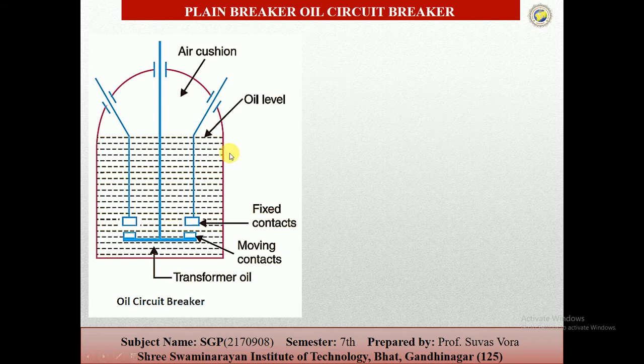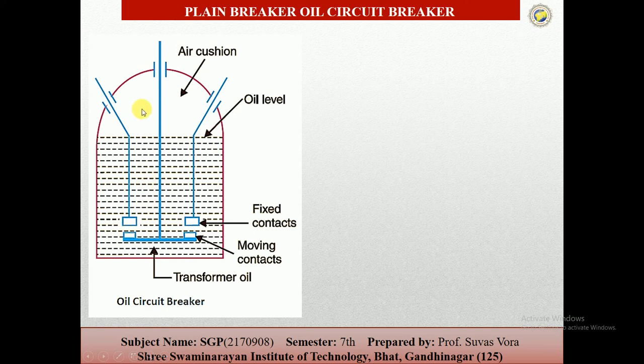These are the basic constructions. These two are the fixed contacts, this one is the moving contact, and this is the transformer oil. This space is the air cushion. When a fault occurs, the circuit breaker opens. At that time the contact moves downward and the arc is generated. The arc is generated by oil chemical reactions, producing bubbles in the tank. After the force of the oil, the arc is quenched.